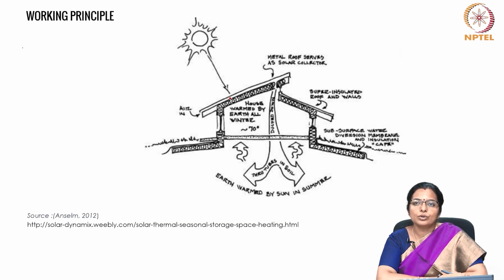The annualized geothermal solar uses a separate solar collector to capture heat. The collected heat is delivered to a storage device such as soil or gravel, or some hotbed or some such structure, sometimes even a water tank, which stores energy either passively by the convection of the heat transfer medium such as air or water, or actively by pumping it. This method is usually implemented with a capacity designed for 6 months of heating.